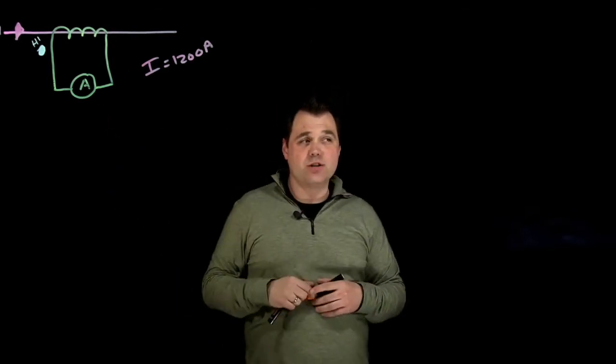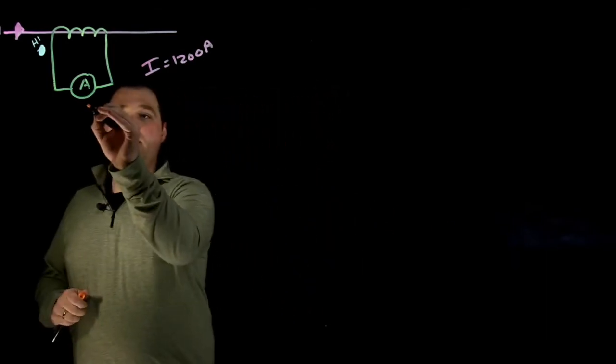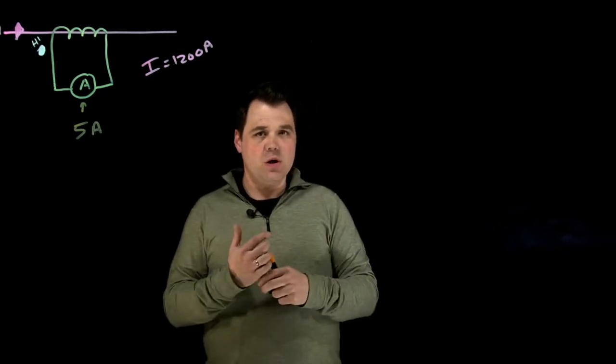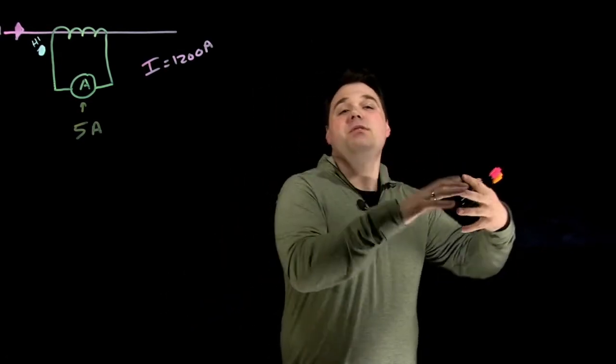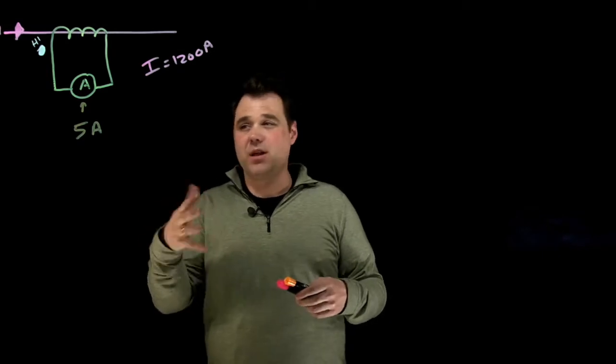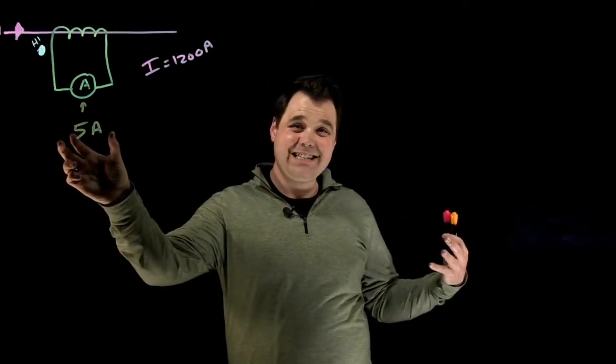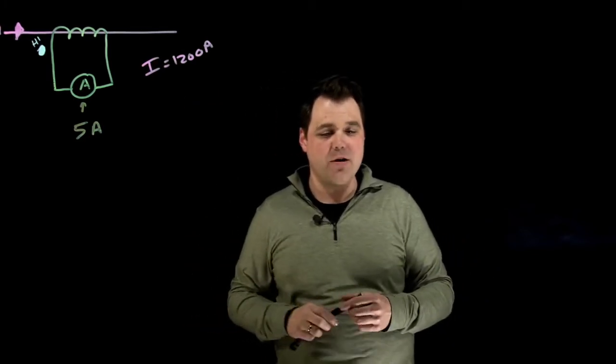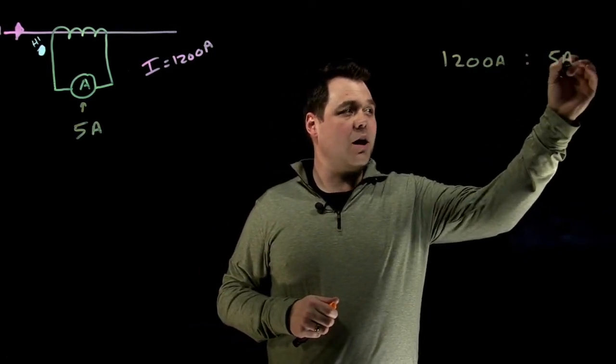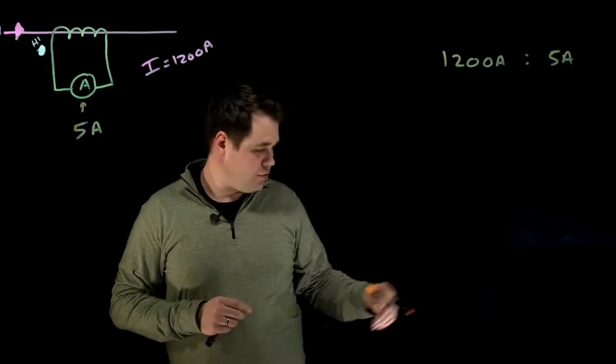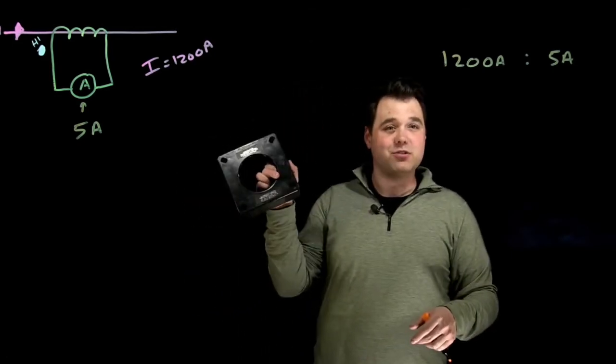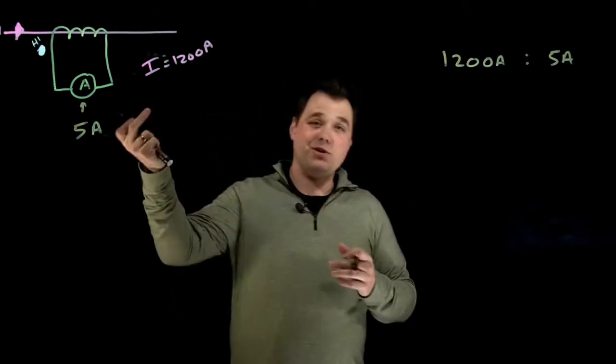Well, the secondary of this current transformer is going to be rated in five amps. So that's what it's going to bring it down to. So that makes it safe, easy to read, and it can then be input into a watt meter for metering. So in this case, to get into a calculation of how that would work, how would I use my value here on my CT in order to know what my actual current is flowing on my primary? Well, like I just said, this is a 1200 amp to five amp CT. The ones I showed you were 10 to five. And this is exactly that, 1200 to five amps. So this would be the exact CT that you could have in this example here.